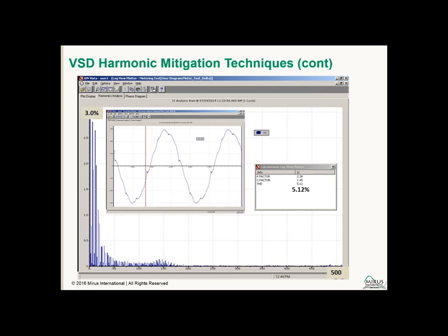This slide shows typical measurement in our test facility. There's a variable speed drive. You can see the input current to the filter that's supplying the variable speed drive. That current is only 5.12% current distortion. And this spectrum shows measurements all the way up to the 500th. So this particular instrument that we're using will measure up to the 500th harmonic.